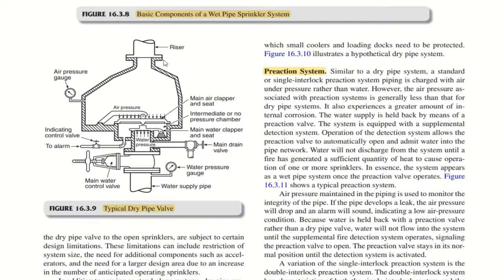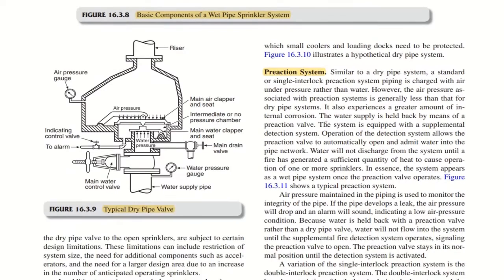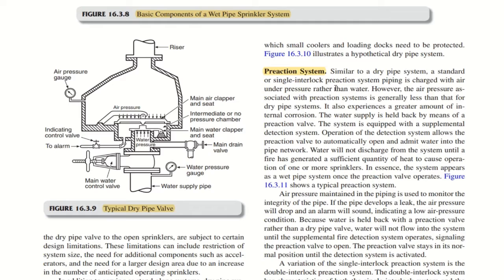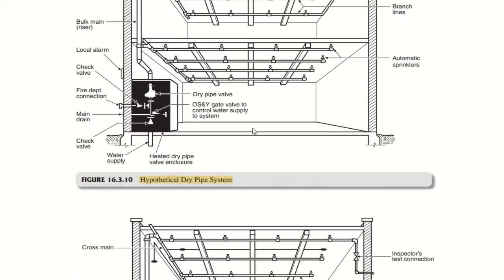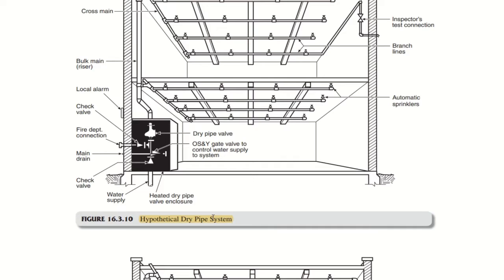So here you have a dry pipe valve. If you want to learn more about this type of system, as I already said, you can go ahead with my video lectures or series which I already posted on the YouTube channel. So the pre-action system is also a dry pipe system, but here it says: similar to a dry pipe system, a standard or single interlock pre-action system piping is charged with air under pressure rather than water. Here you have a hypothetical dry pipe system.